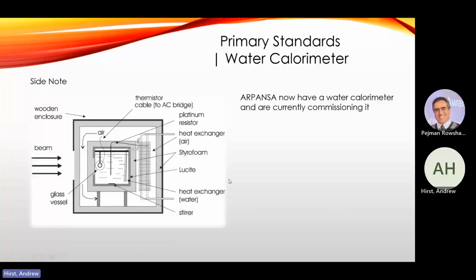Just a side note, they also have a water calorimeter now. They're just currently commissioning it, so they're going to swap over to the water calorimeter. The obvious benefit is that you don't have to do that conversion between dose to graphite and dose to water, so you can actually lower your uncertainties. But there are a lot of other correction factors and things you have to take into account when using the water calorimeter.